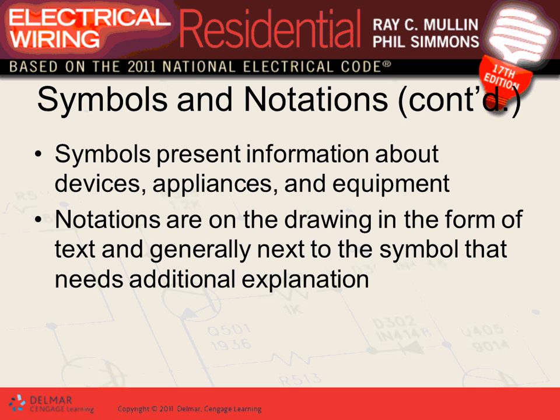Then with symbols, we have something called notification. A notification is written right next to the symbol, like GFCI. So what does that mean? That's going to be a GFCI receptacle. Right next to it, you can put 72 above finished floor, meaning I want this receptacle 72 inches above the finished floor. So you put notes next to the devices to give installers more information.